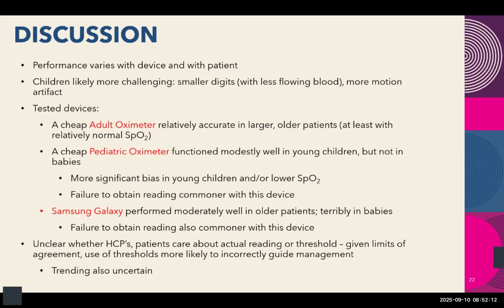If you're moving around a lot and you're measuring someone's O2 sat with any device, you have venous blood, which is moving, sloshing around. And these machines look for blood which is sloshing around. They don't care whether it's arterial blood or venous blood. So if you're sloshing around appropriately, the machine will start measuring your venous O2 sat, which is extremely cool but useless. But that's why these machines often measure falsely low rather than falsely high. The bottom line was the cheap adult oximeter worked pretty well for people with relatively normal sats who are pretty big. The cheap pediatric oximeter worked kind of so-so and didn't work at all in babies. And it had a significant failure rate. Once again, the smartphone oximeter worked reasonably well in older people who weren't moving very much and where it took a long time to get your measurement. It worked terribly in little kids and especially in babies.